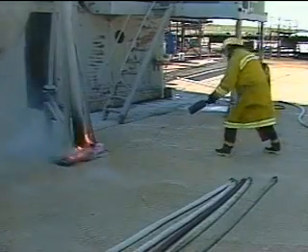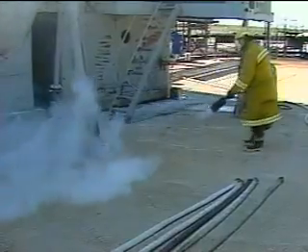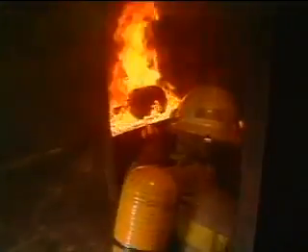Concerning CO2 extinguishers. CO2 extinguishers generate static electricity, which may be a source of ignition. CO2 extinguishers can be used on small Class A and B type fires, but are most effective on Class B and C fires in enclosed spaces. In open areas, such as on deck, CO2 extinguishers may be ineffective due to wind velocity.